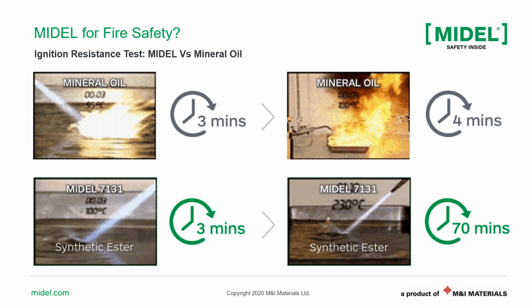After 3 minutes, the bulk liquid temperature reached 100 degrees with no localized ignition. After a further 70 minutes, with the bulk liquid temperature reaching 230 degrees, you still don't have any localized ignition. So I thought to share this as a simple test to indicate why the K-class classification shows that these fluids are less flammable, and so allows users to reduce the spacing between them and reduce the risk of fire if you are using K-class esters in your transformer.